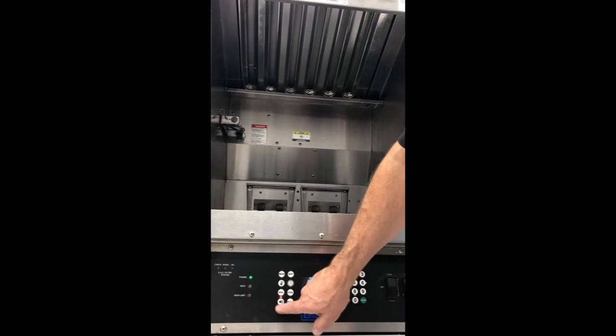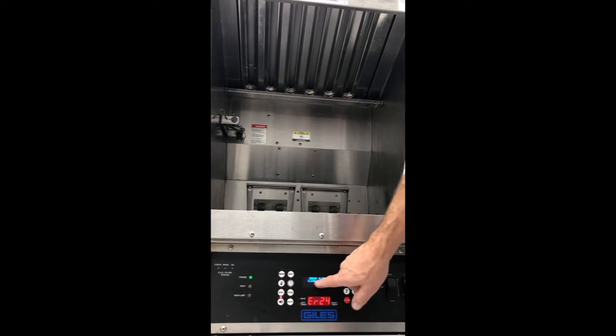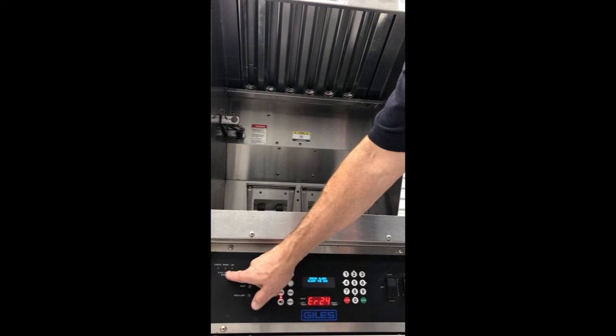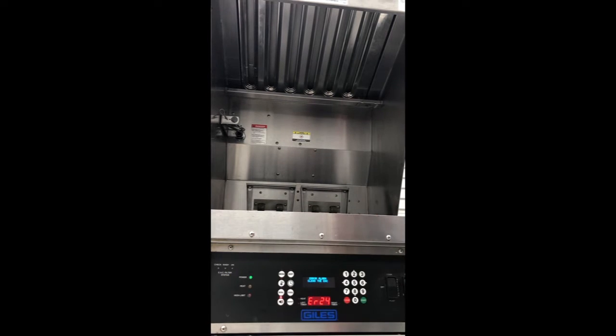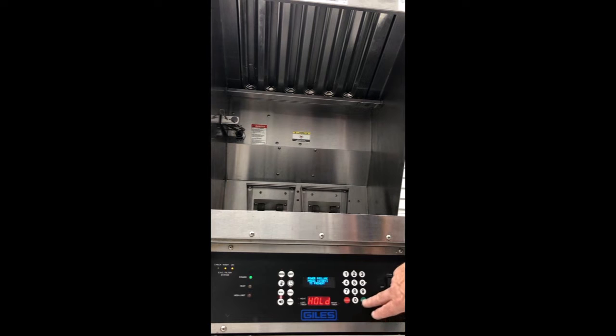Any of your ventless fryers are going to come up with that. We can silence that. And it says error, clean the EAC. You'll notice that all the lights have shut off, signifying that we've now killed the power to that driver board. That keeps us from damaging that driver board if someone has a bad filter and they just keep pushing it in, pulling it out, pushing it in. Or if they just turn the power on and off to repeat it. Just like now, if I turn it off, when I turn it back on, the power comes back on, but it'll go back into alarm because that on light is still on.